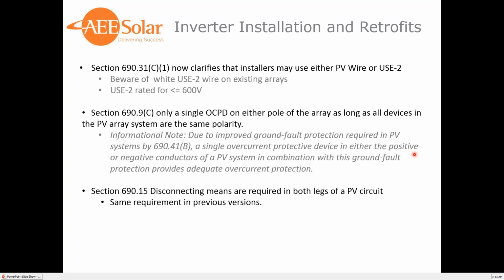Another thing to be aware of is USE-2 is typically rated for less than or equal to 600 volts. So if you're doing a commercial project with 1,000 volts, be sure that the conductor you're using is rated for its use or rated for the voltage.